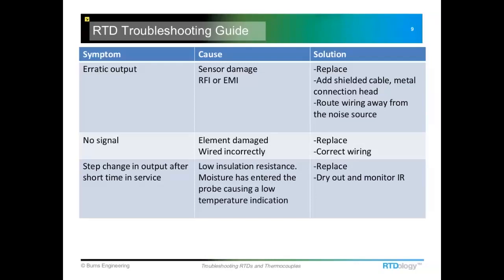The only solution is to replace the probe and maybe look at one that's more durable, or reposition the sensor to a location farther away from shock or vibration. One common place for mechanical shock to damage a sensor is in a pipeline with a steam injector just upstream of the temperature probe — when steam shoots into the pipe, it can cause a water hammer that will destroy an RTD in a very short amount of time.